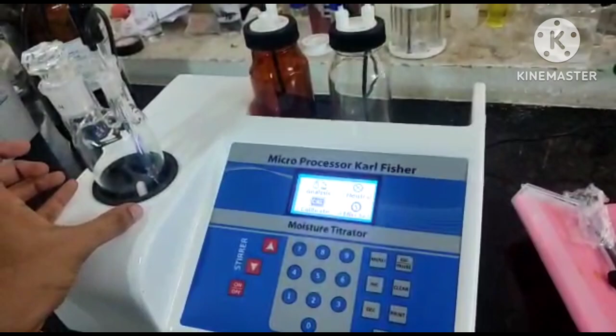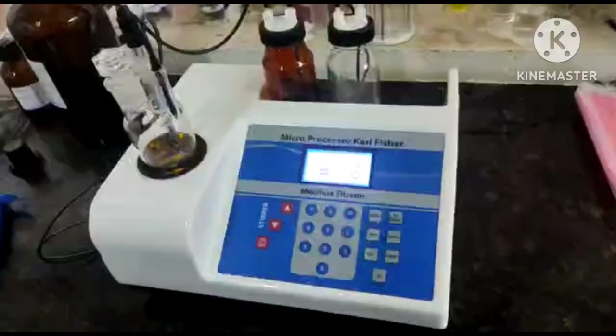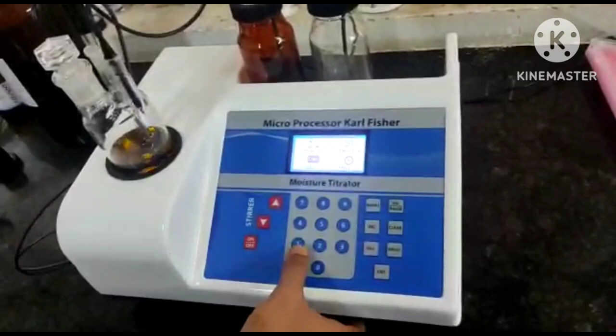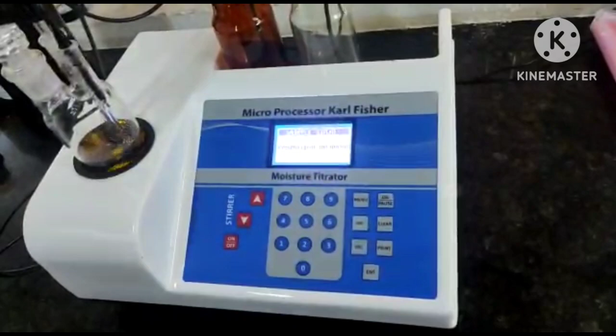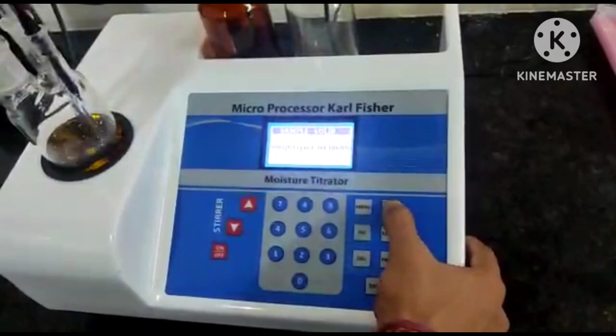For 35 to 40 ml of dried methanol or HPLC grade methanol, the Karl Fischer reagent, and then the silica gel. Next option is sample analysis, the option number 1. So for analyzing the sample, we have to go for option number 1. Then we need to select what kind of sample we have, like solid or liquid. In solid, suppose I have selected solid, then we have to put the weight of your solid sample. These two digits are for grams, and after the dot the digits are for milligrams. So this is for solid. Thereafter, if we select liquid, then along with the volume of your sample, these two are in ml and these are in microliters. So along with the volume of the sample, we have to put the density of your liquid solution also. So these are the things in liquid. Other things are the same. This is the general difference.